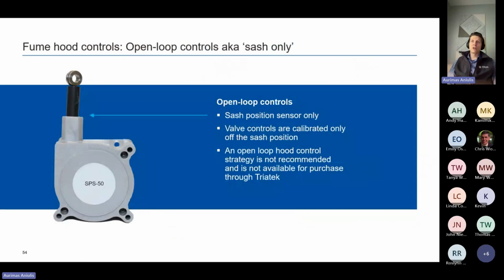Some companies offer what we call open loop controls, aka sash-only fume hood controls. What that means is I'm not measuring air or pressure or velocity in real time. I'm calculating it only based on my sash position, my opening area, and I'm just trusting that there's air in the system. I'm trusting that the valve is doing what it's supposed to be doing so that my calculated value is correct. Interesting. Is there a better way to ensure safety other than calculations?